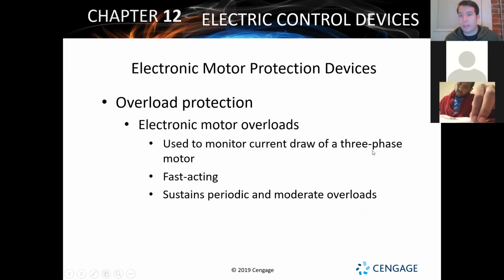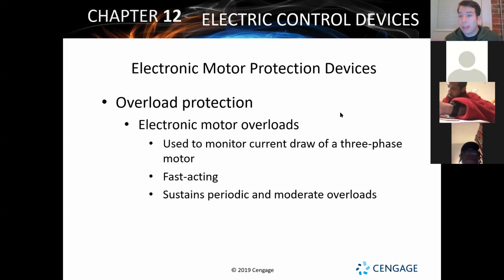So we talked about overload protection the other day on Monday. Overloads, the most common thing we can have go wrong with the system is that system overloading or overdrawing on amperage. It's going to have a lot of energy going through it at one time. So to prevent that from, like we were talking about before, heating up, overheating, damaging our wiring and components and everything, the overload is really there to make sure that when that level of electricity is present and comes through the system, we shut the system down before it gets to the components.